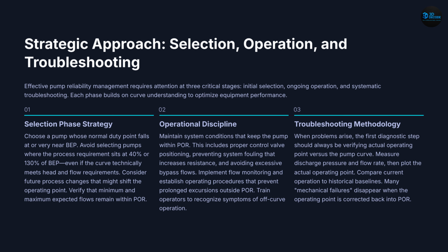Slide 11. Engineering strategy. In the selection stage, choose a pump with duty point near BEP. During operation, maintain flow within the preferred region. During troubleshooting, always check the actual operating point first. This is the correct engineering approach.